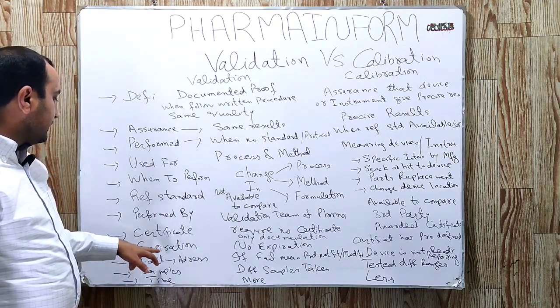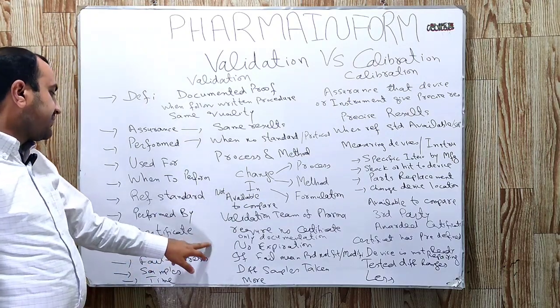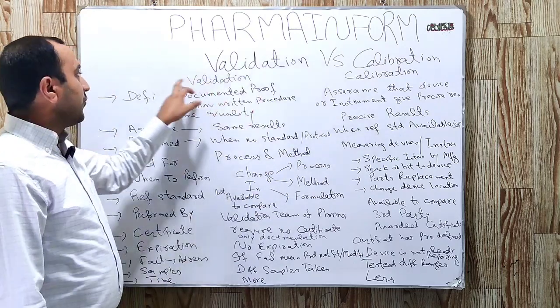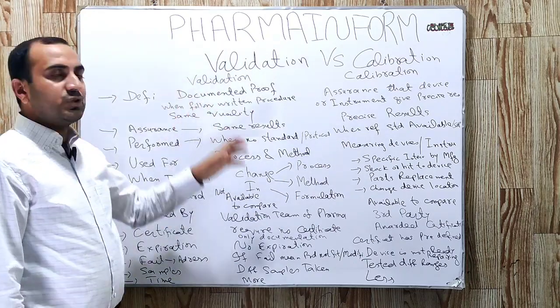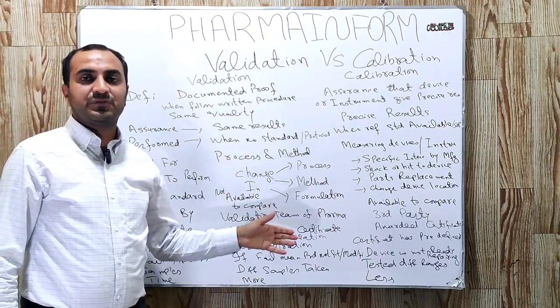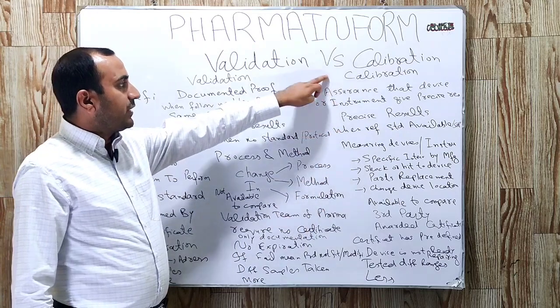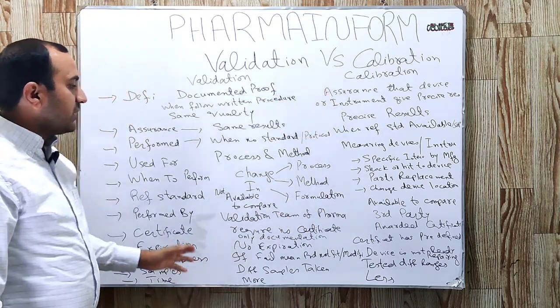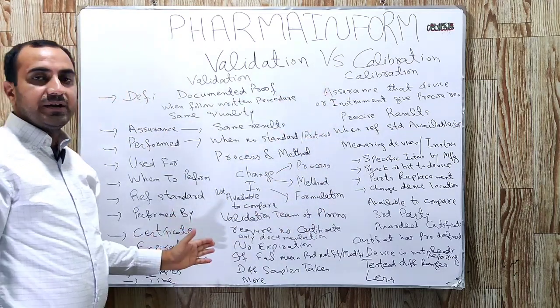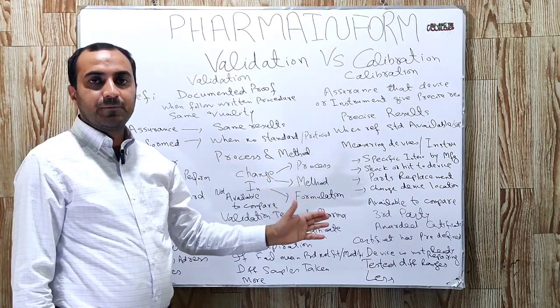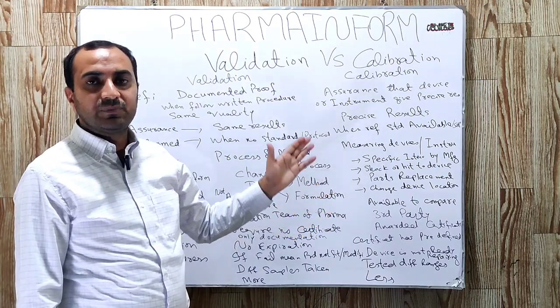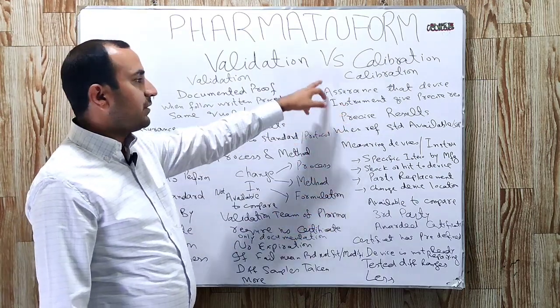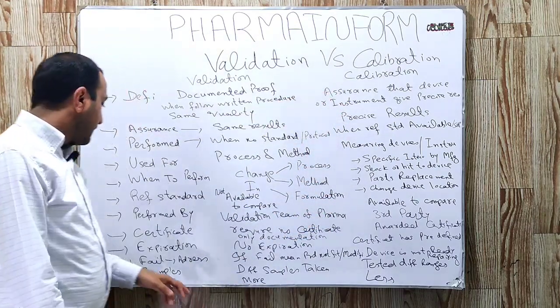Regarding expiration: for validation, there is no specific expiry date. For calibration, we follow the expiry date provided by the third party, which is mentioned on the certificate of calibration.